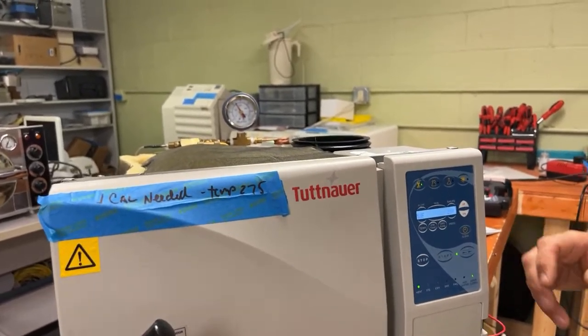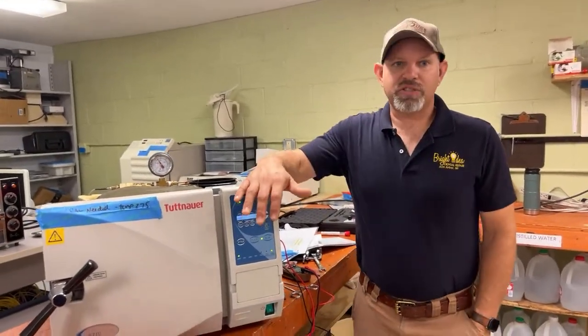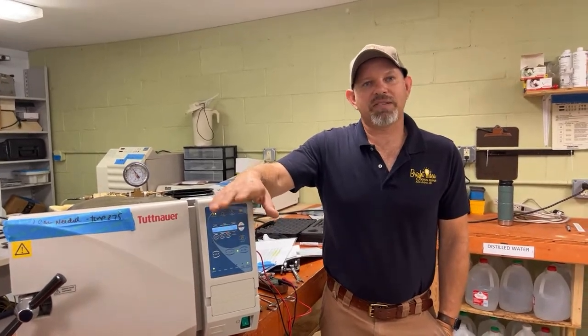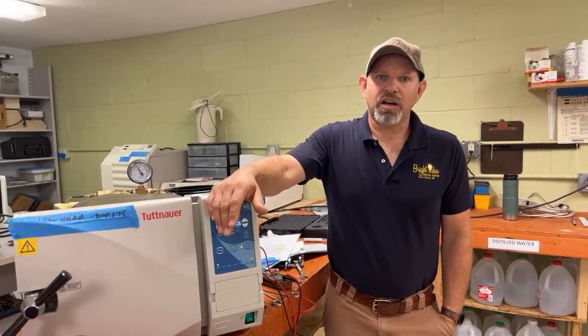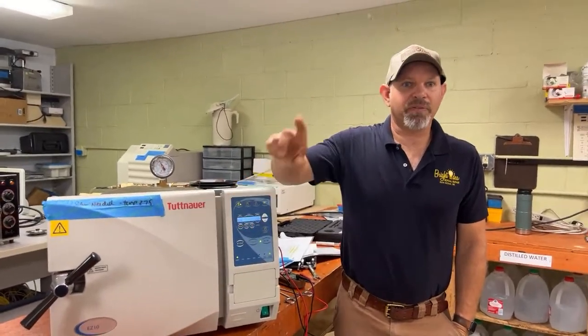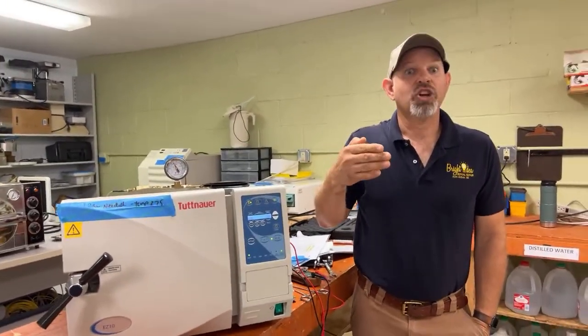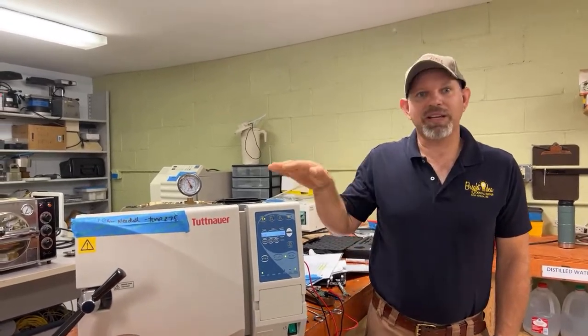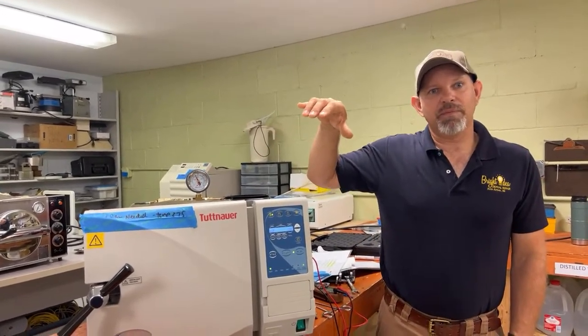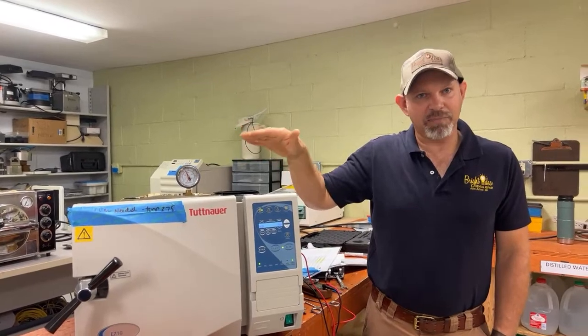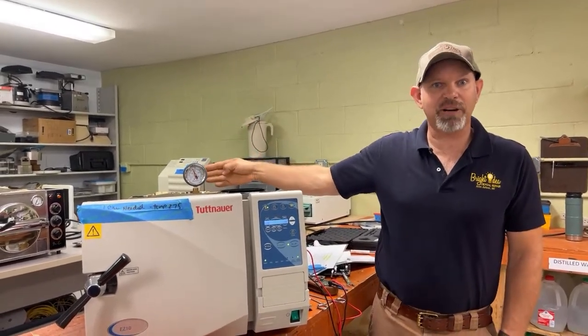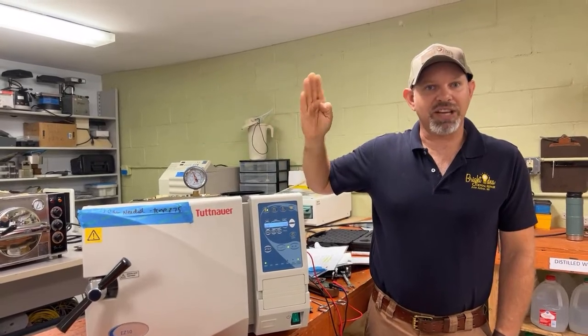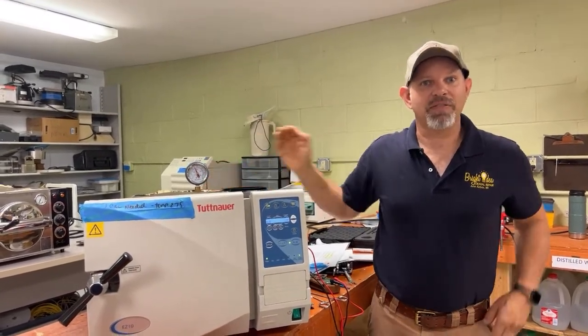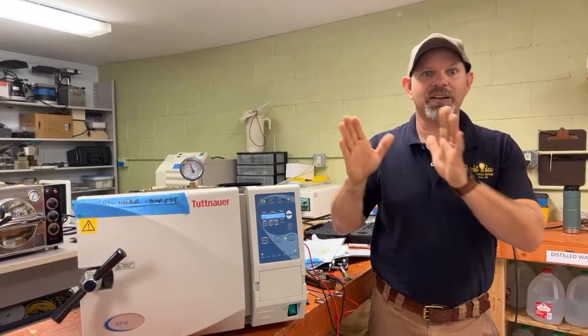We do have a question. Okay, awesome. How do we know when our equipment needs calibration? So typically the manufacturer recommends that preventive maintenance is done every year. During the preventive maintenance, you should be running a thermometer. If your thermometer is out of spec with your display, like, that's actually what happened with that one. We put a thermometer in it, it read 260, but the display read 270. That caused me to stop and say, okay, let me go ahead and look further into it.